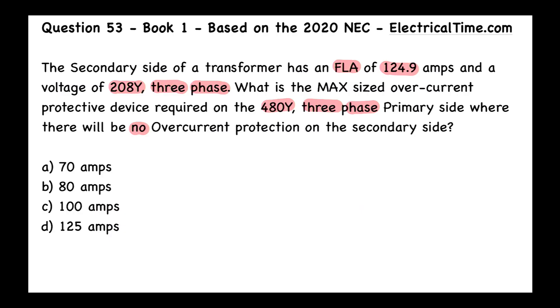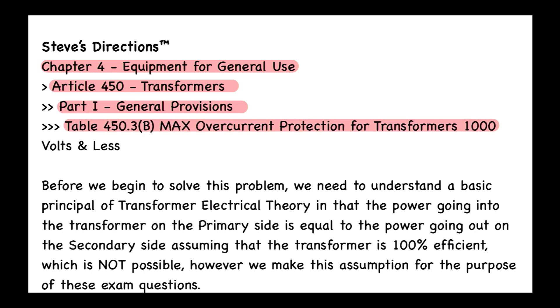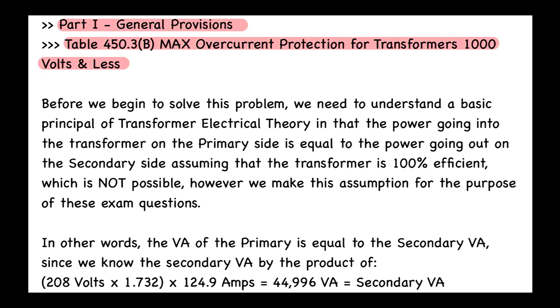The answer is A — 70 amps. The first question to ask is what article applies here: that's Article 450 for transformers, within Chapter 4, Equipment for General Use. Inside Article 450, Part 1 for general provisions, we find Table 450.3(B), which is called the max overcurrent protection for transformers 1000 volts and less.